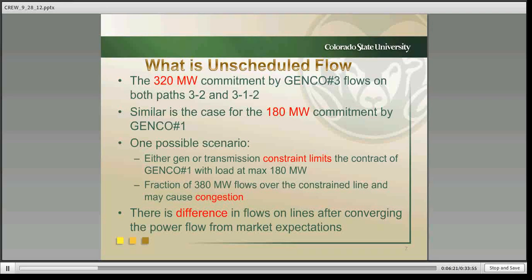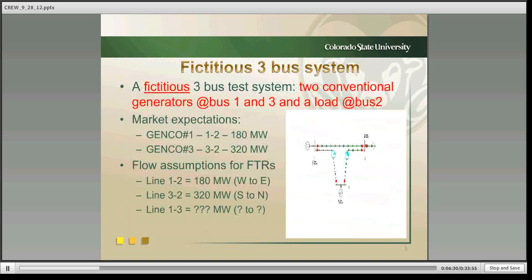Now what is the disadvantage of having an unscheduled flow? For example, in this network, if there was transmission congestion or a path limitation on this line, 1 to 2, and we have some unscheduled flow flowing over this line, which superimposes itself though it's not allocated, it's going to cause congestion.